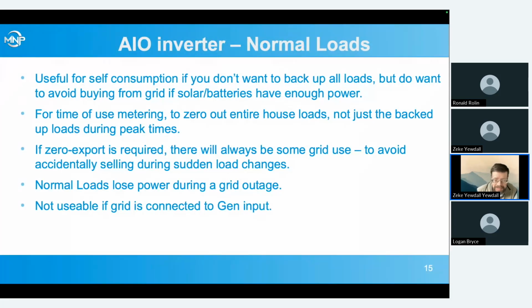Another thing to realize is, of course, these normal loads will lose power during a grid outage. They're on the grid panel, they're on the grid side of that isolation relay in the inverter. The grid goes out, it's going to open that relay and it can't support those normal loads. So it's only when the grid is up that we're doing this. And obviously, if we've connected the grid to the generator input instead of the grid input because we don't want to inadvertently export to the grid, we can't support normal loads through the gen input. It will never sell power to the generator because that's really bad for generators. So if we're pretending that the grid is just a generator, we can't do the support normal loads.